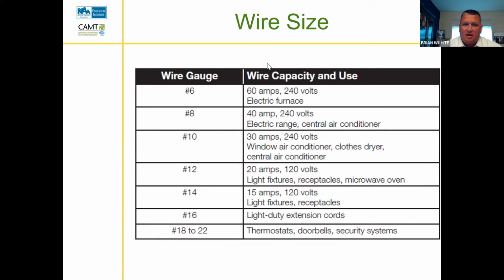Now, wire size. We talked about wire size in our skill check, and that comes into play based upon the amount of current or the amount of amps something needs to carry. For example, in our very first line here, 240 volt electric furnace, we're carrying 60 amps. And so we have to have a larger diameter wire. So the smaller the number, the bigger the diameter of wire. So in this case, they're using 6-gauge wire. Common in our industry, we're in that 12 to 14 range for our 120 volt receptacles.